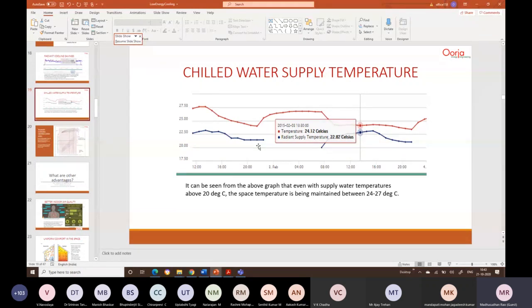Or there should be air at higher dew point, which means even if you want to operate this space at a higher temperature, 27 degrees 50% RH, still the floor temperature is much higher than the dew point. So the only possibility where the condensation will occur is when untreated air comes into a building, through cracks, fissures, or doors that are not closed. These kind of situations where the building is not airtight. So that is one thing people have to take care of. The building has to be airtight. Even in air conditioning, the building has to be airtight.